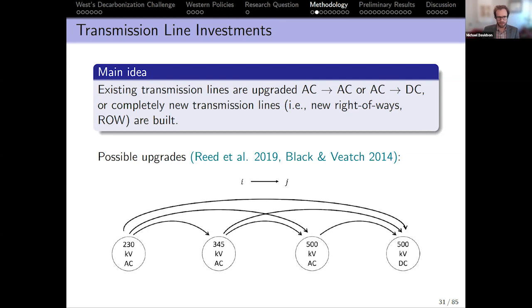So we're actually considering in this model upgrading a lot of different options for existing transmission lines. We went out and collected the existing as well as the proposed transmission lines and their paths. There are different ways depending on the current voltage of the line. If it's 230 kV now, you could upgrade it to various higher AC voltages, as well as upgrading to a 500 kV DC line, which would give you lower losses over long distances. If you're already at a 500 kV AC line, you could upgrade just to 500 kV DC. There's a couple of different configurations, and we model each of these potentials.